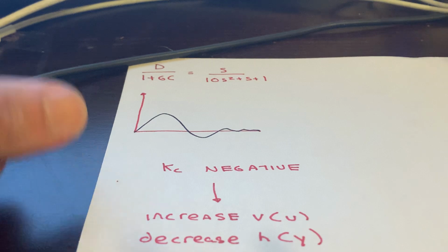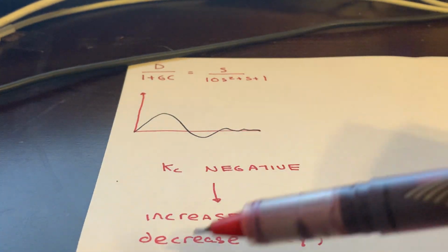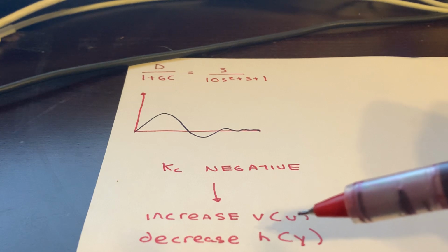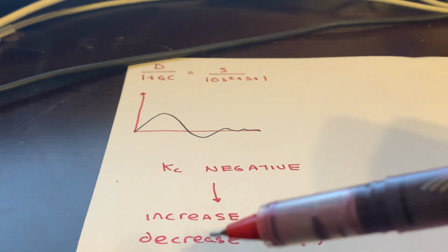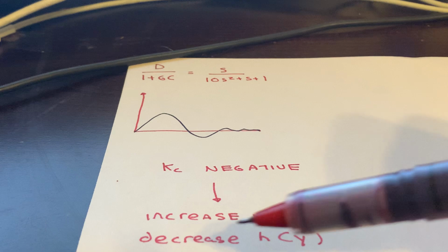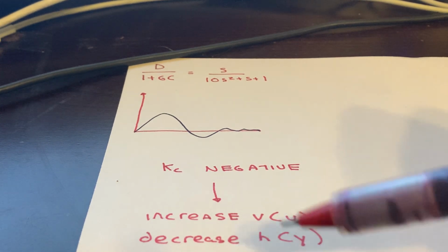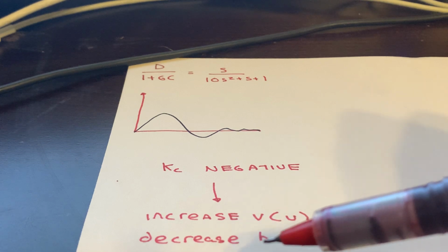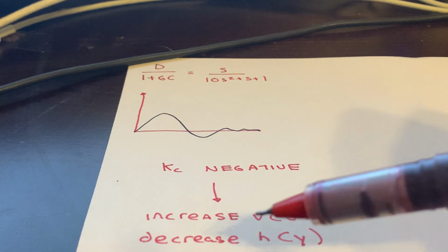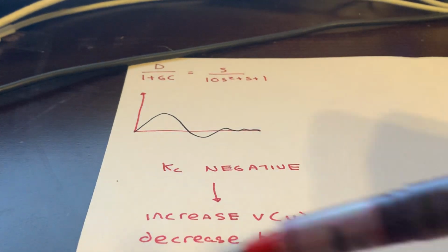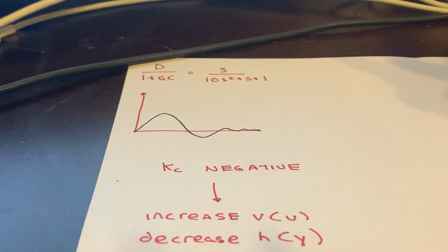The other way I think about it is, in our canonical problem, when we increase the input, we increase the output. But when we have a negative gain, basically when we increase the input, we're actually decreasing the output. So our input was the valve position and H, the height, which are U and our Y. And because this is a negative relationship, we also want our gain to be negative. And that's kind of like a reverse acting controller. And so that kind of finishes problem number 5.